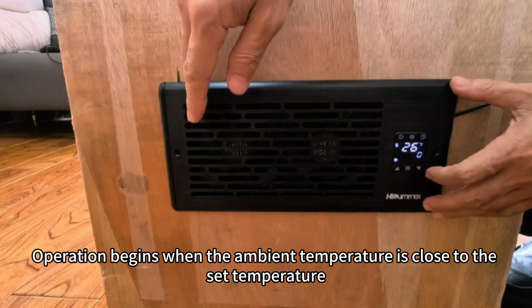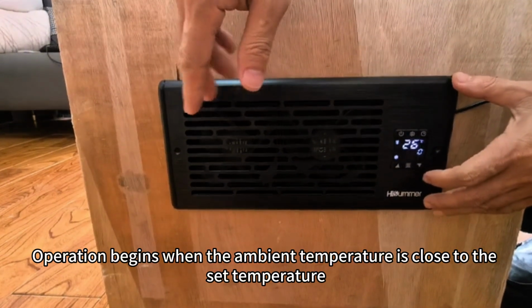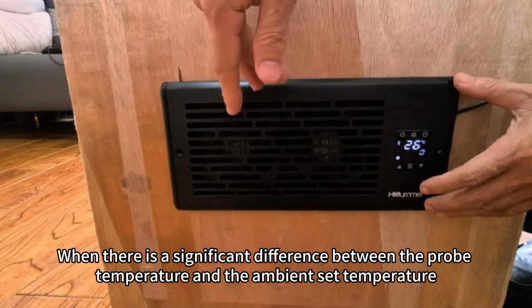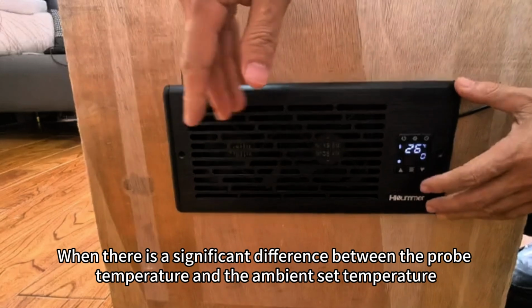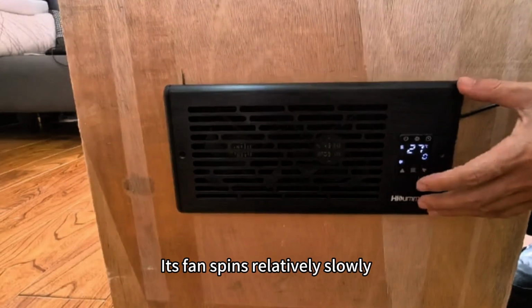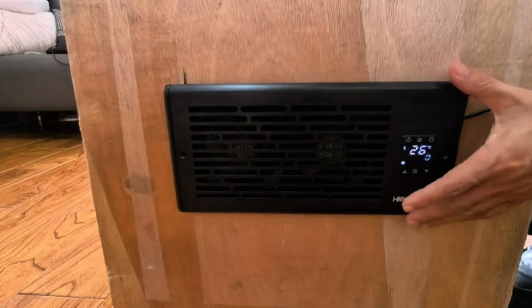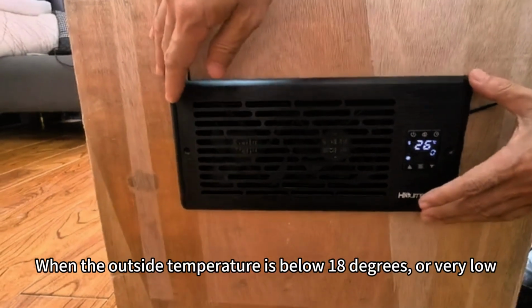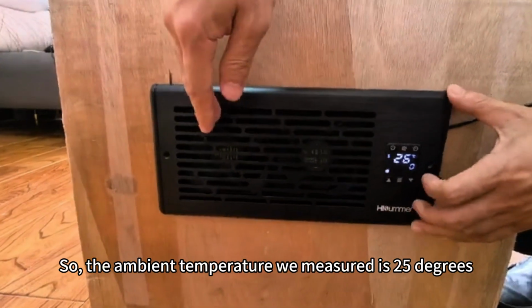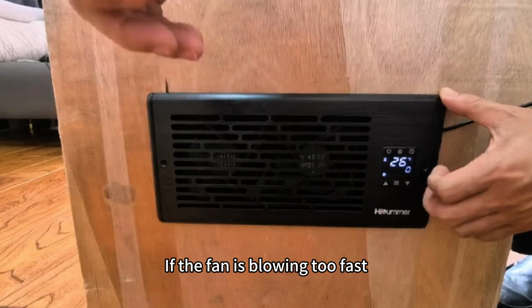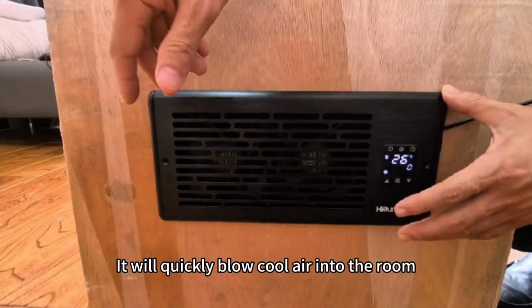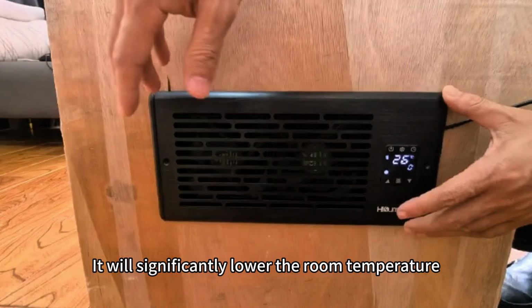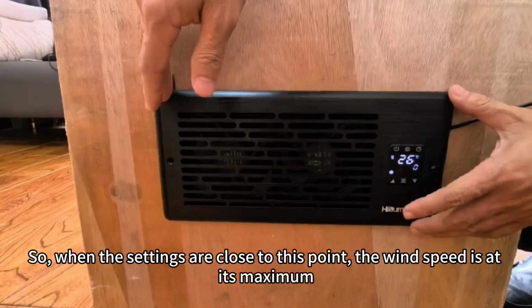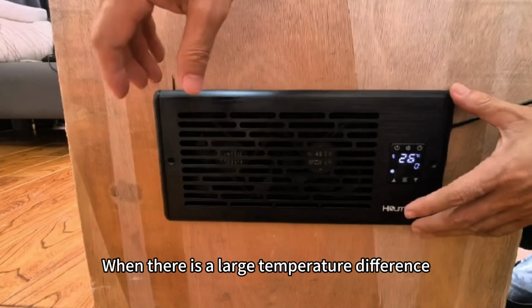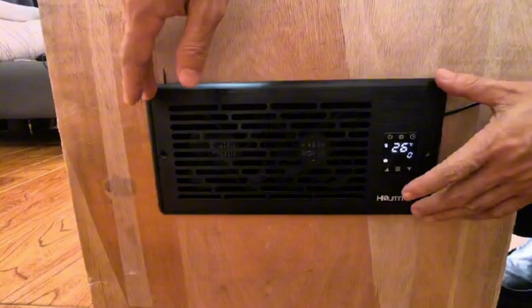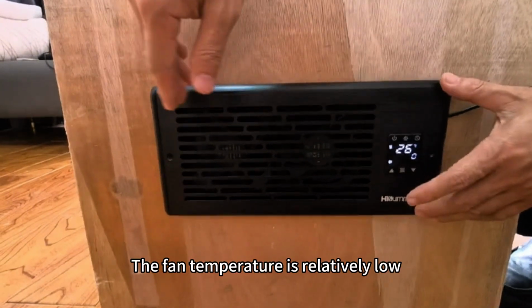Operation begins when the ambient temperature is close to the set temperature. This is the highest wind speed. When there is a significant difference between the probe temperature and the ambient set temperature, its fan spins relatively slowly. The reason why? When the outside temperature is below 18 degrees, or very low, and the ambient temperature we measured is 25 degrees, if the fan is blowing too fast, it will quickly blow cool air into the room. It will significantly lower the room temperature. So, when the settings are close to this point, the wind speed is at its maximum. When there is a large temperature difference, the fan speed is relatively low.